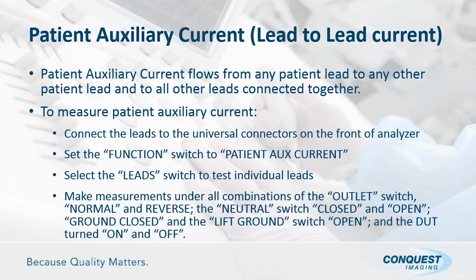Now we're talking patient auxiliary current, which is lead to lead, and this is again an ECG function. Patient auxiliary current flows from any patient lead to any other patient lead, and to all other leads for that matter when connected. So that's what you're measuring. Connect the leads to the universal connectors on the front of the analyzer. Set the function switch to patient auxiliary current, or aux current, and select the leads switch to test individual leads. And again, nothing's changed. You have to make these measurements under on, off, normal, reverse, open, close. So make sure you meet all the requirements of the different conditions while you're recording your results.